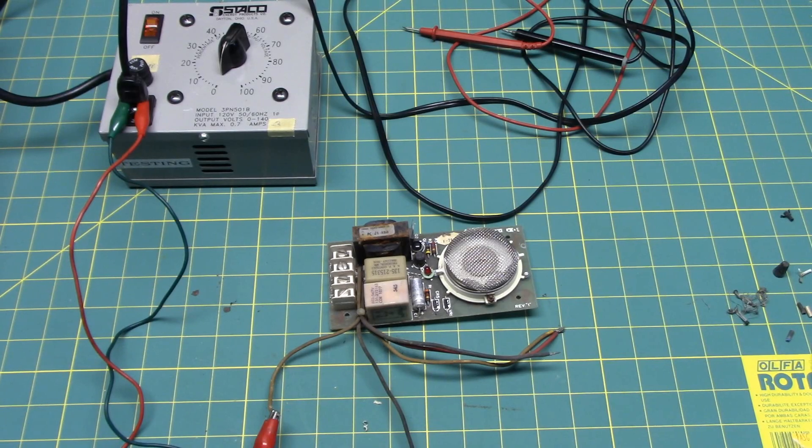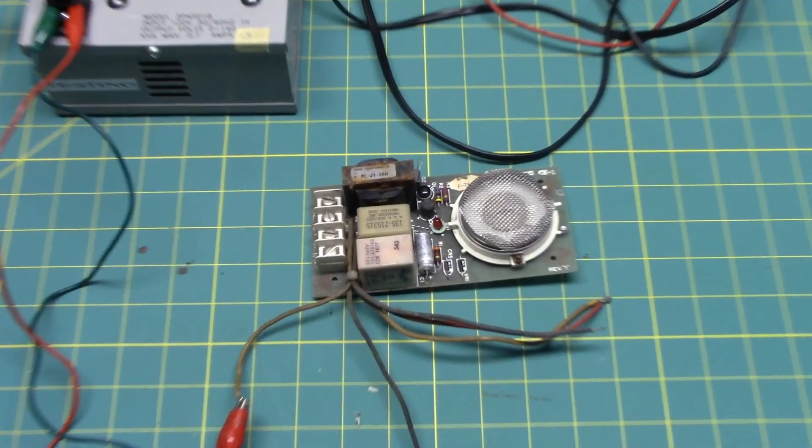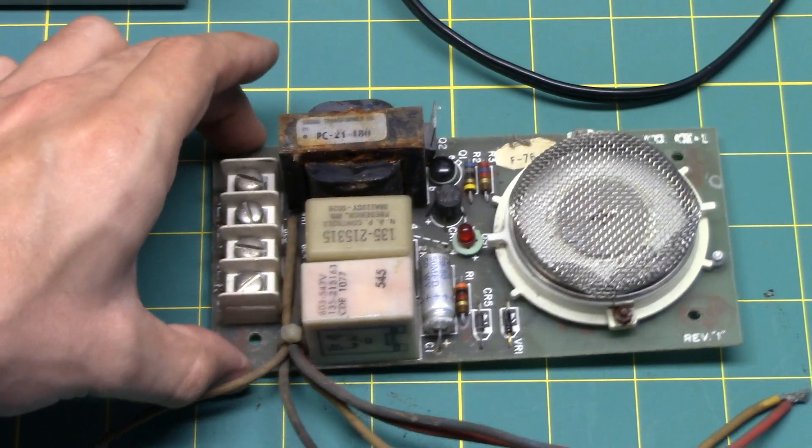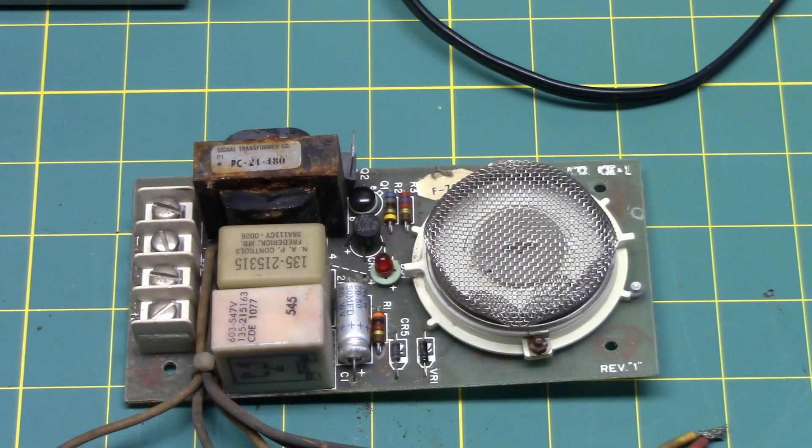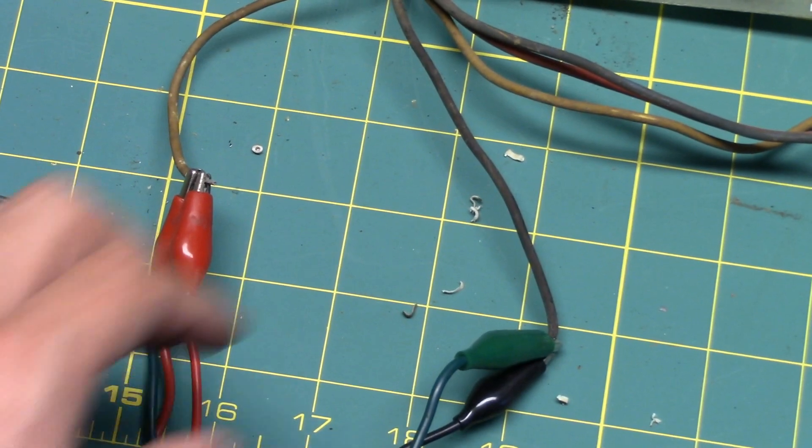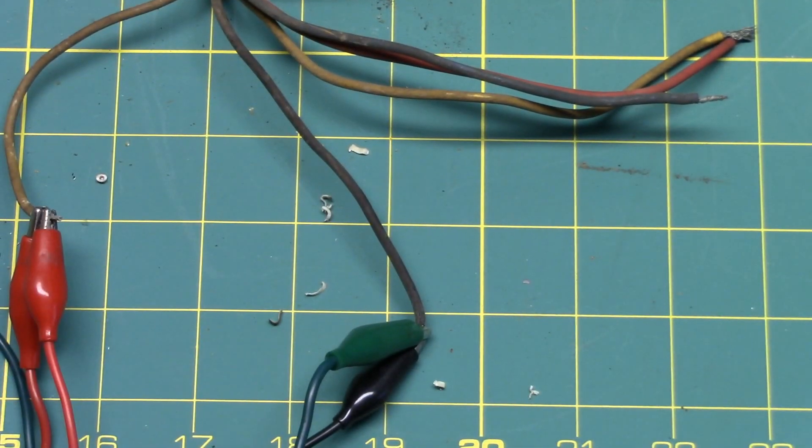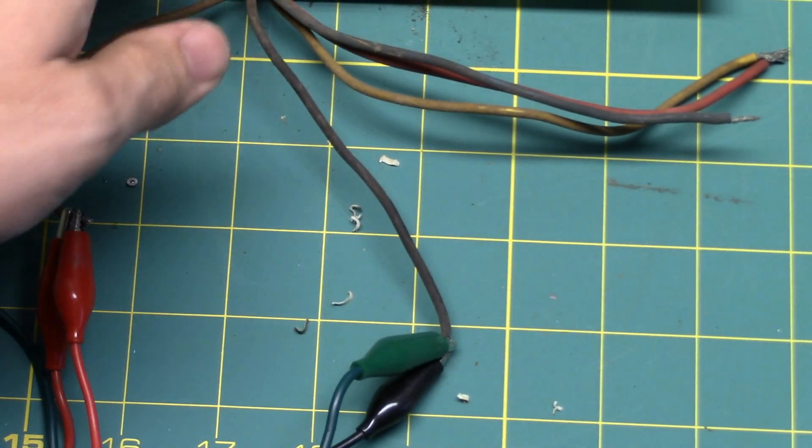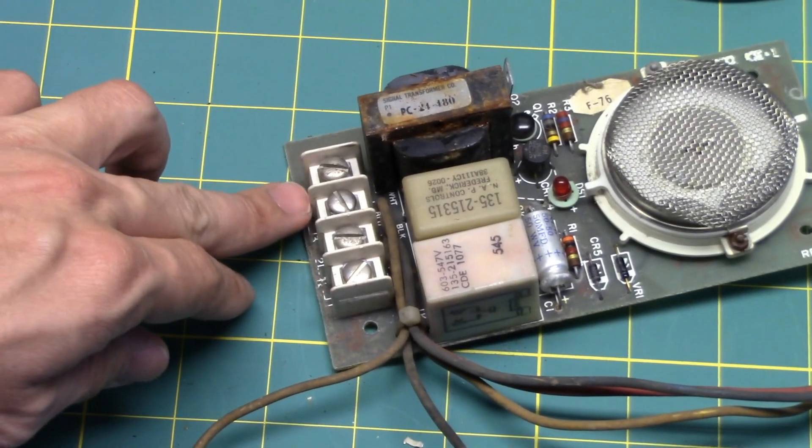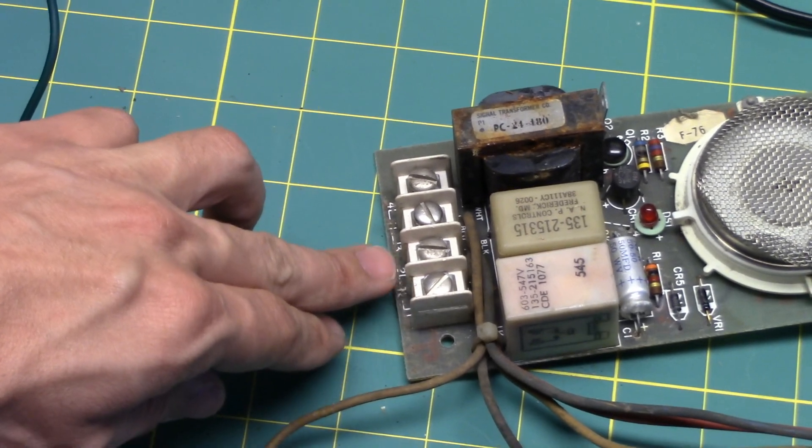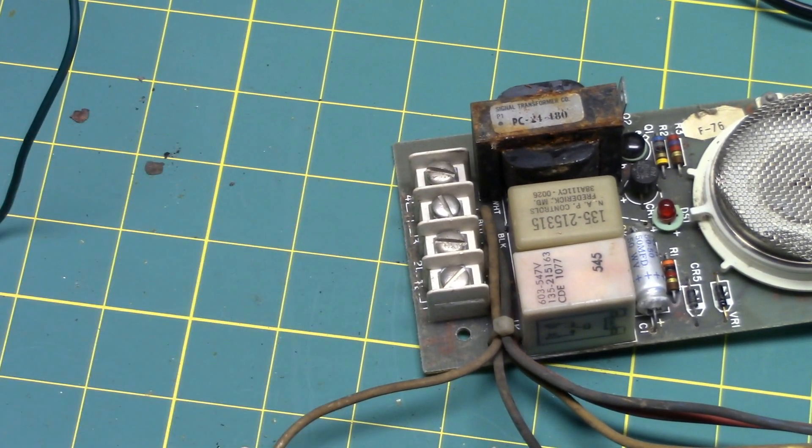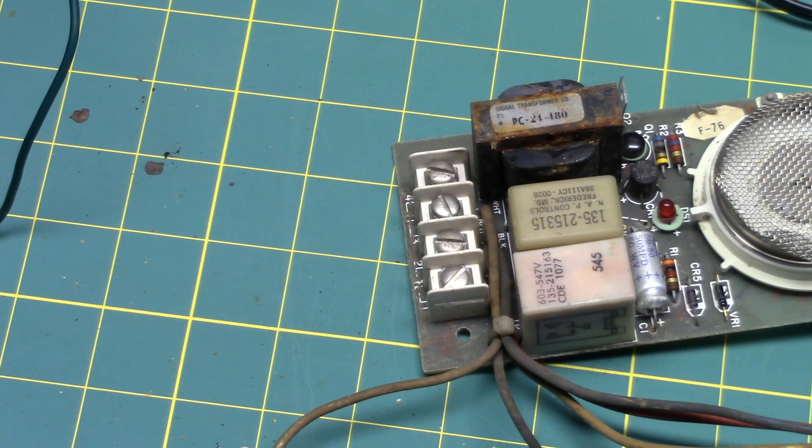So I got this detector hooked up right here. Unfortunately, its ionization chamber is squashed, but that does not electrically alter its function. I have 120 volt wires connected right here. And so far, only the normally open output right here is working. The normally closed one here, the contact isn't making or breaking. It's probably a soldering joint or a relay connection or something like that.